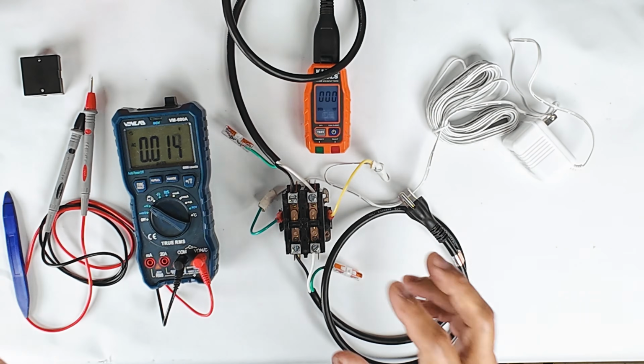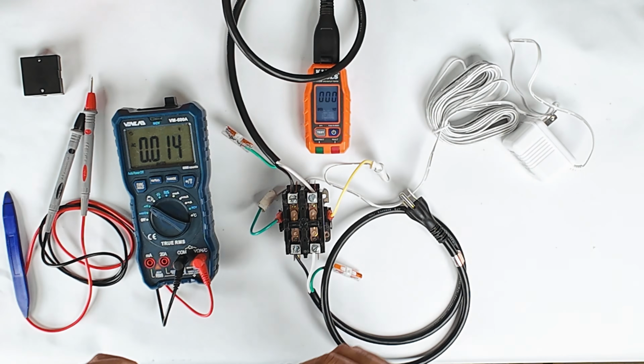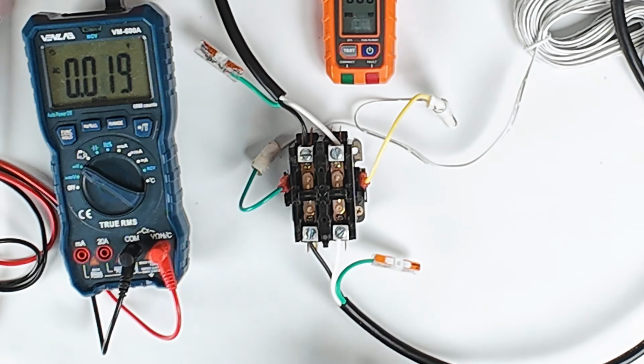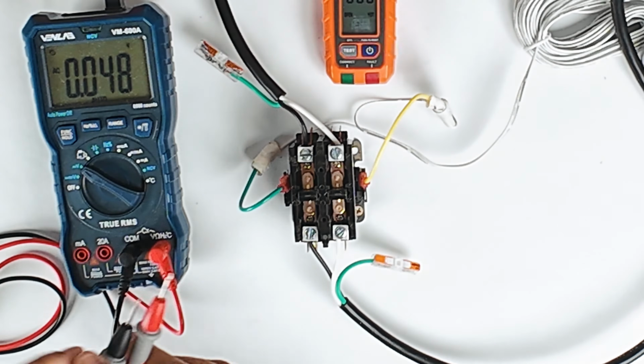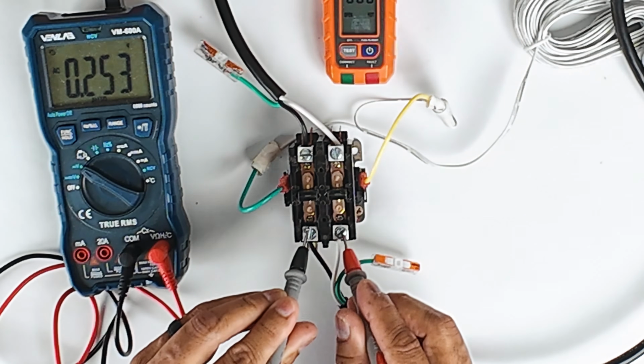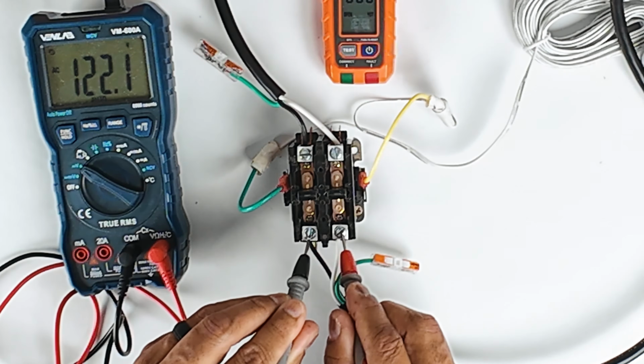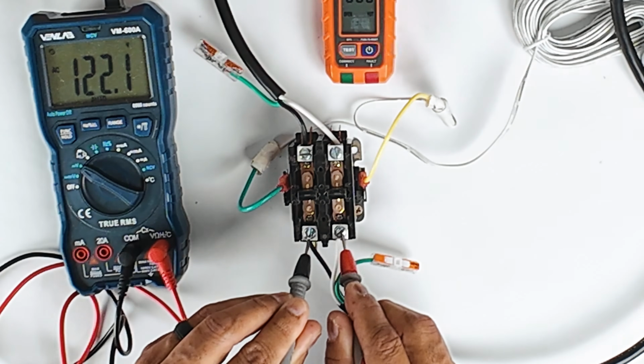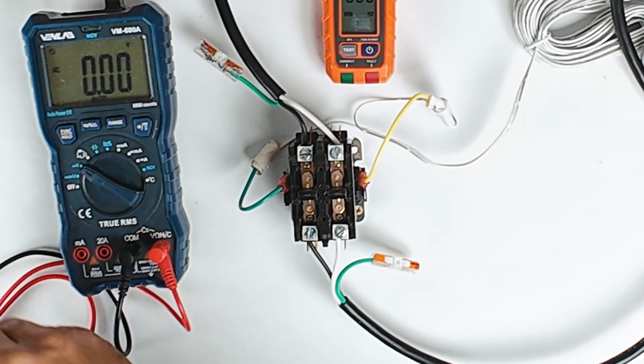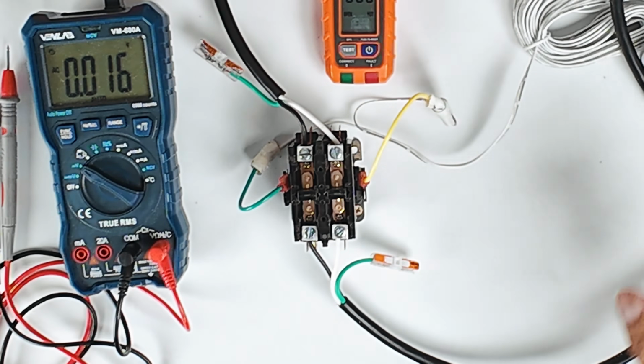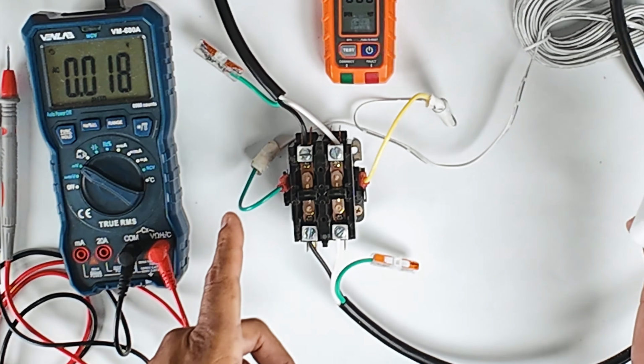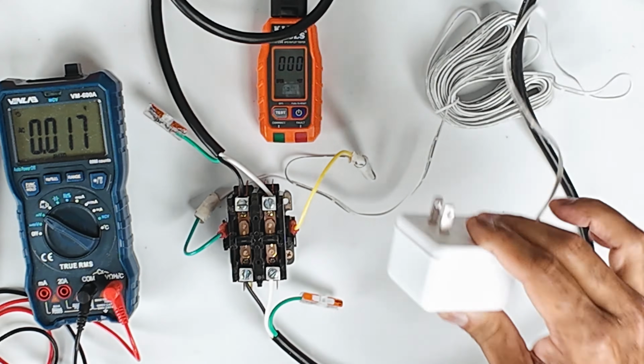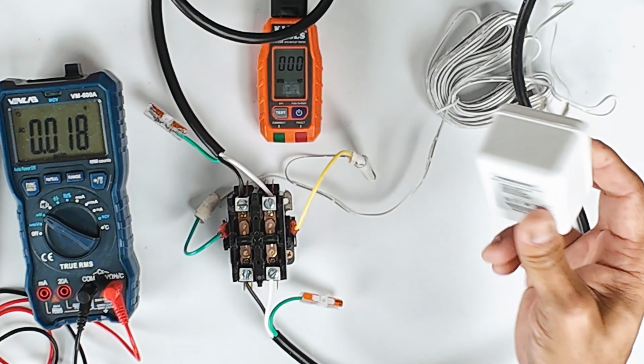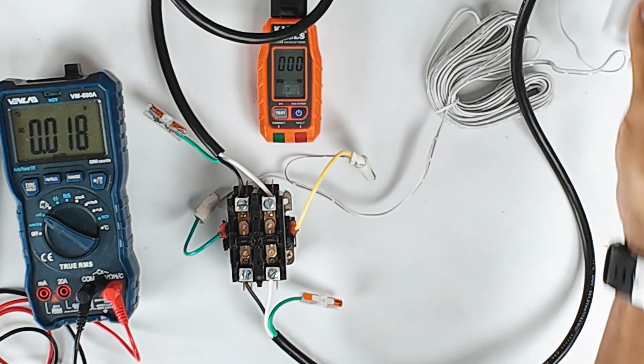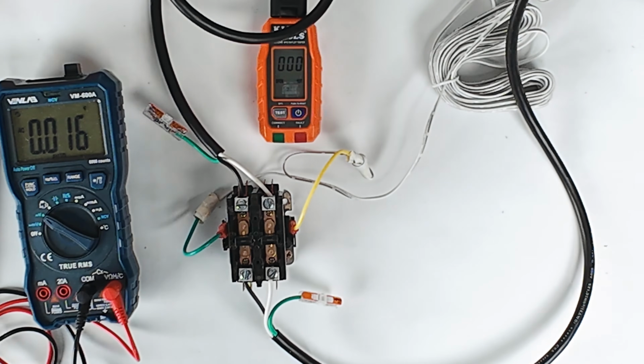Now let's talk about how this works in a normal circumstance. So we have our contactor plugged in. Now we should have power coming in at the bottom here. This should be 120 volts. As you can see on my meter, we have 120 volts coming in. Now, whenever our thermostat calls for cooling, 24 volts is going to be sent to this coil.